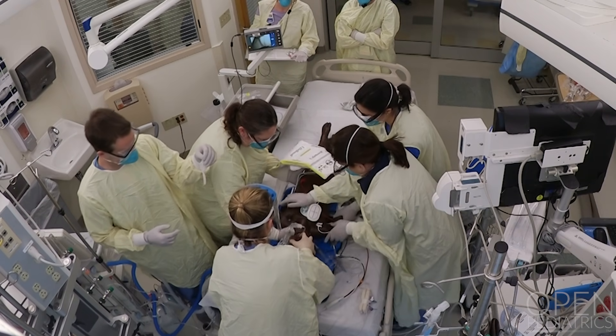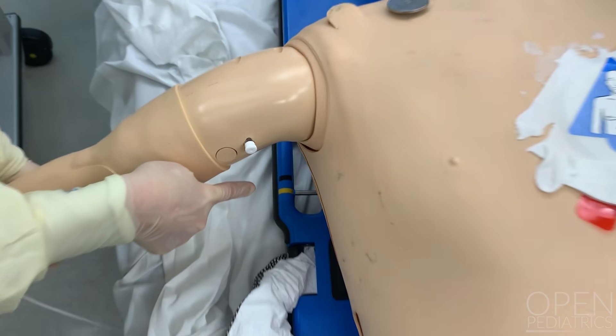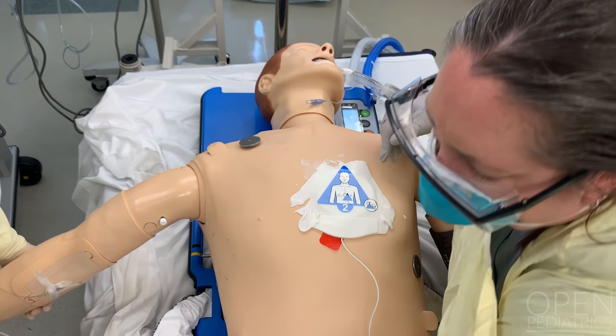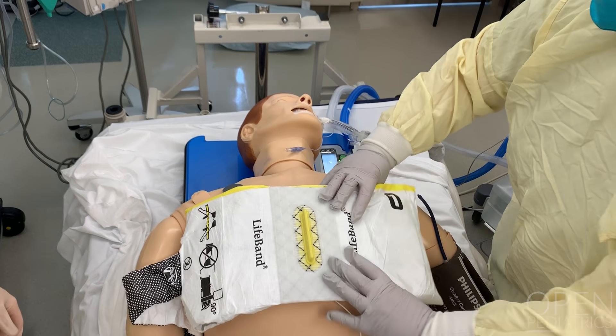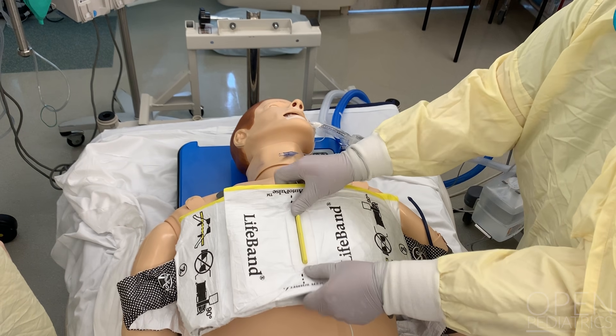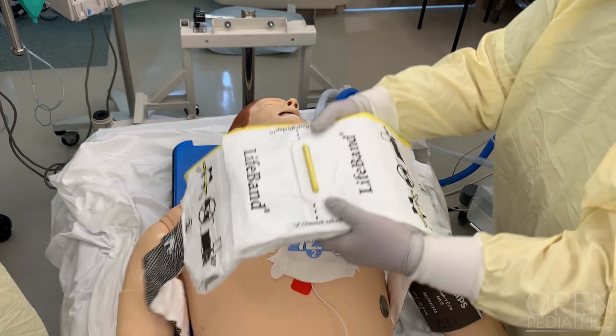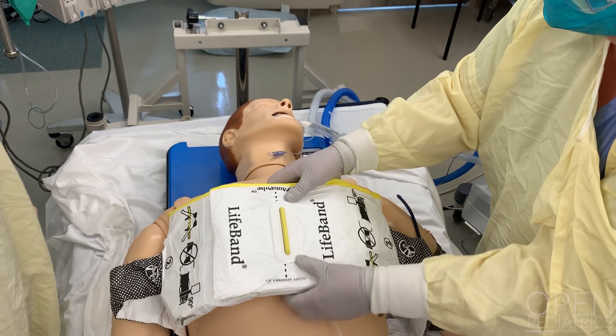To align the patient on the mechanical CPR platform, they may need to be moved — match their armpits level with the yellow guideline on the device. Next, wrap the compression band around the patient: place side 1 on the chest first, then close the band by bringing over side 2, guiding the yellow tab on side 1 through the slot on side 2, securing it with Velcro on each side. Pull the life band up to its fullest extension to set the internal motor to its starting position and ensure the bands are untwisted. Place the band back down onto the patient's chest so the yellow tab sits on the sternum, directly over where manual chest compressions would be performed.